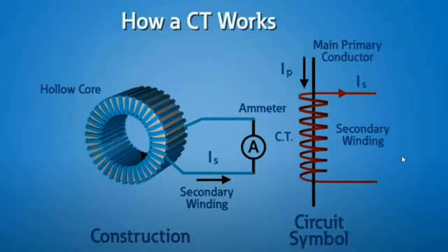Now I am going to explain about the current transformer. The large alternating current, which cannot be sensed or passed through a normal ammeter and current coil of wattmeters, energy meters, can easily be measured by use of current transformers along with normal low voltage range instruments or low range instruments. A transformer is a device which consists of two windings called primary and secondary. It transfers energy from one side to another with suitable change in level of current or voltage.